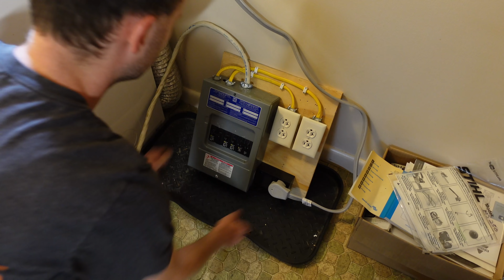Alright guys, this is where the test gets interesting. On my Batrium display, we're pulling 5,500 watts from these batteries currently. These batteries are rated for a maximum load of 6,000 watts when in series like this. I can already feel these cables getting a little warm. 109 amps is a little much for 6 gauge wire. As you can hear, the fan on the inverter has turned on, which runs based on temperature or load percentage.